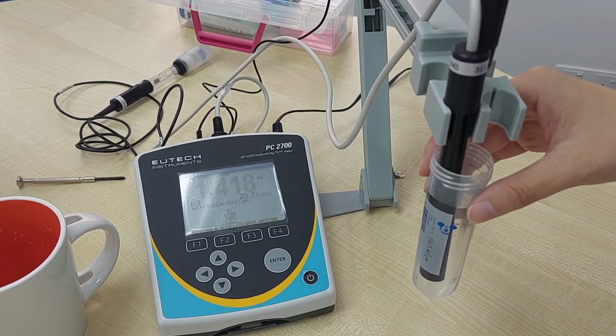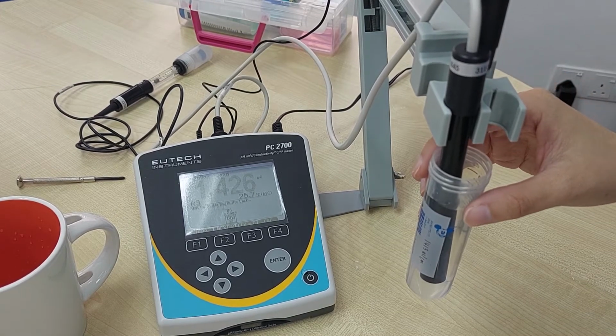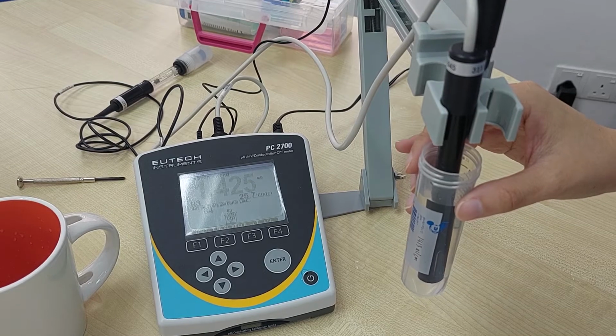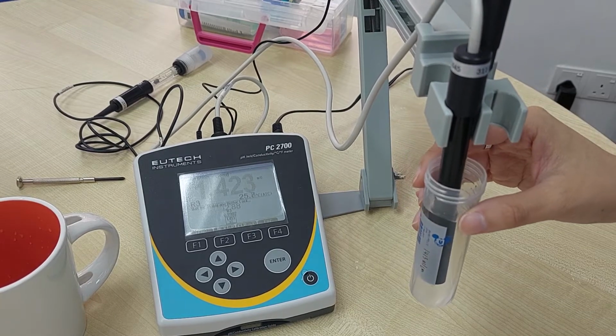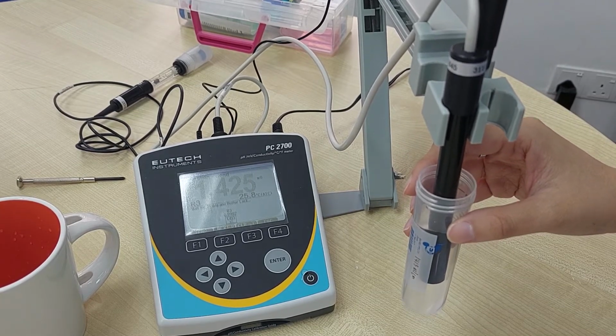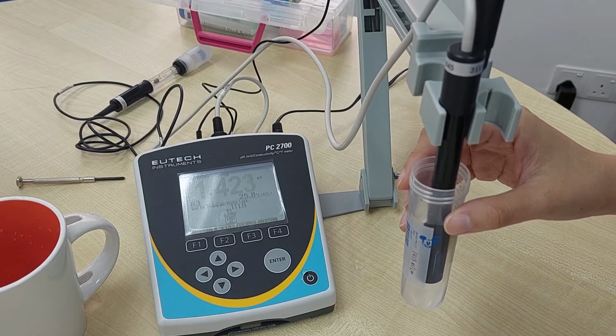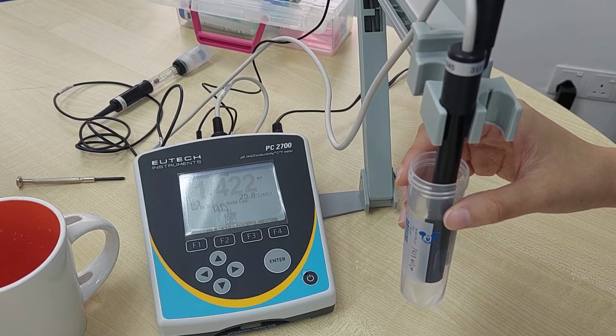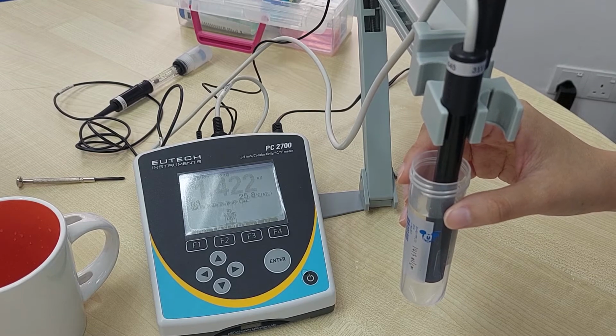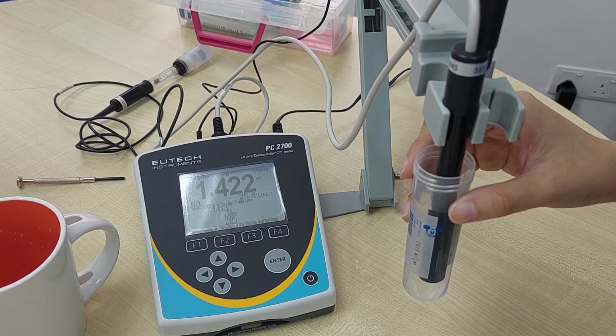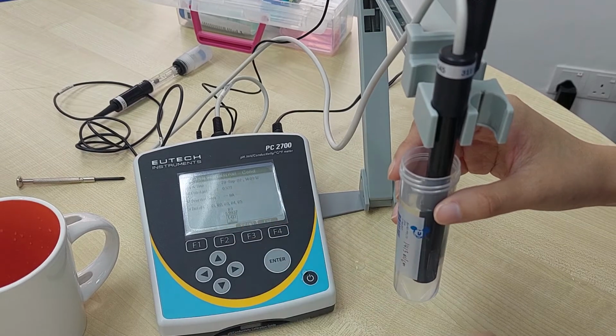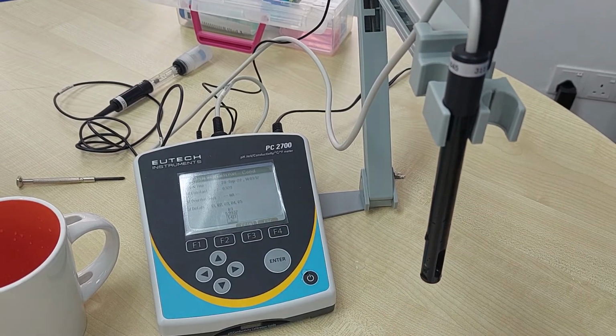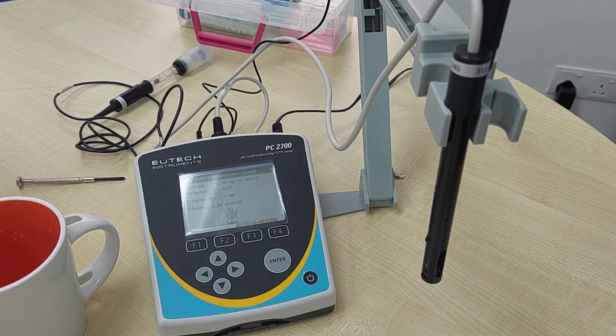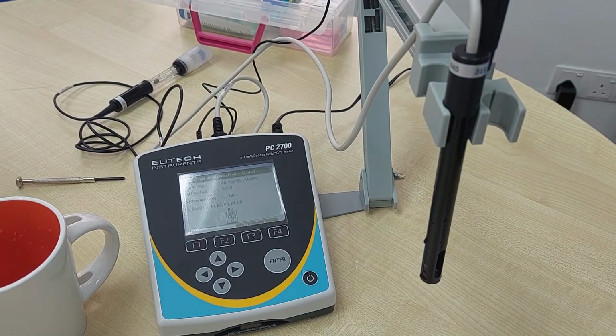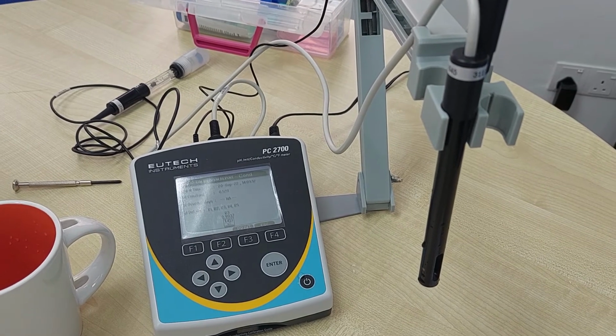Okay, same, we'll wait for it to stable. Okay, once it's stable, press enter. Alright, so the conductivity calibration is done. So conductivity is much easier. You just need to calibrate one point that is nearest to your sample range.